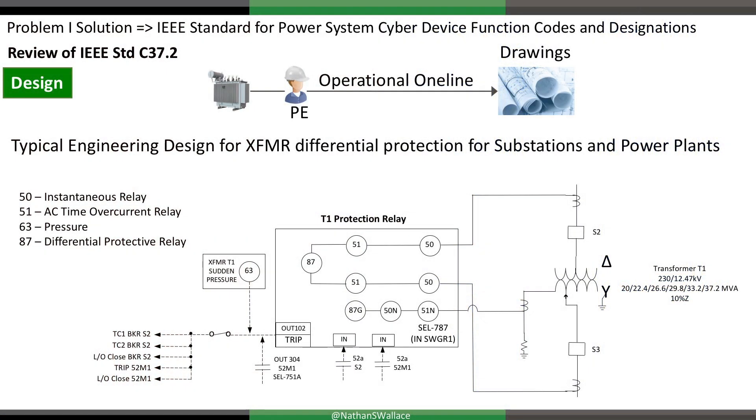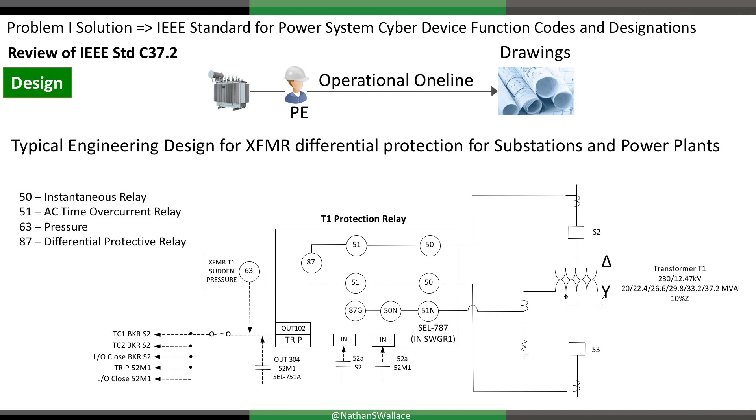Let me show you what I mean. This is an example of an operational one-line. The licensed professional engineer says, I want to protect this transformer. As a design engineer, I'd show my instrumentation transformers — CTs, PTs — and the signals coming in. You can see function code 50 for instantaneous relay, 51 for AC time overcurrent, and 87 for differential. There's a differential calculation — if there is a differential, trip. So this is an input going into a black box; the syntax '87' represents the function being performed inside that black box, and the operation is a trip — trip the breaker. How can we mirror this with cyber?